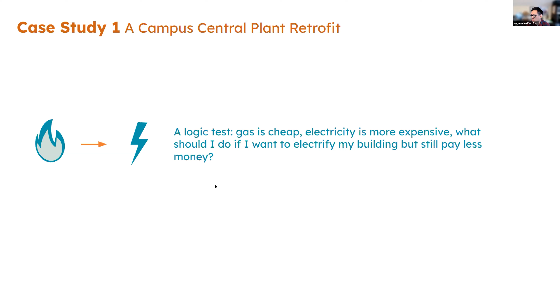What is the scope? It's a pretty typical campus central plant, a combined heat and power plant, meaning they have a gas turbine and a steam generator, plus chillers, cooling towers, and thermal energy storage (TES). A very common setup for university campuses is that if you have steam on site, you generate steam for electricity and have steam turbine chillers, using the steam to run chillers for cooling.